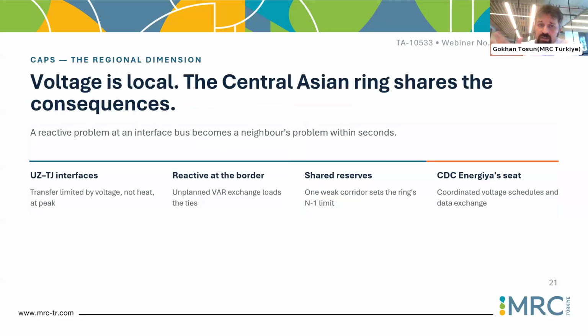Well, definitely voltage is a local issue, but at the same time, especially for interconnected systems, the consequences are shared. Any voltage-triggered or overall system issue can be experienced in the neighboring bus bars. So the issues in terms of reactive reserves, shared reserves, are also an important aspect, especially for interconnected regions. For the Central Asia power system, we have the CDC Energia, which manages different perspectives of the overall dispatch operations. But a local problem also has an overall impact on the interconnected system. So that was also one of the messages.